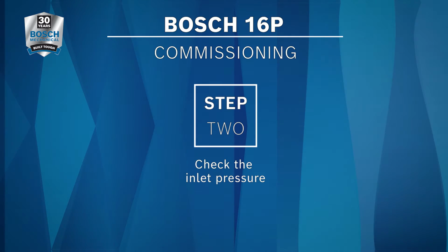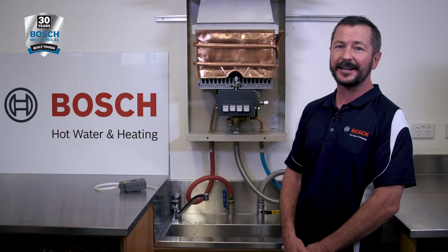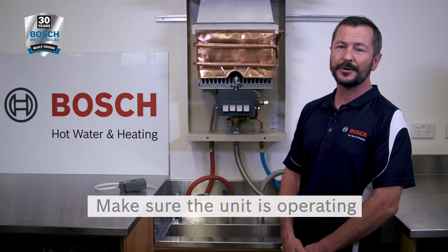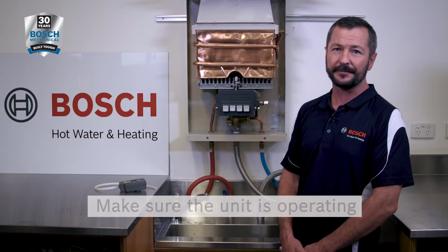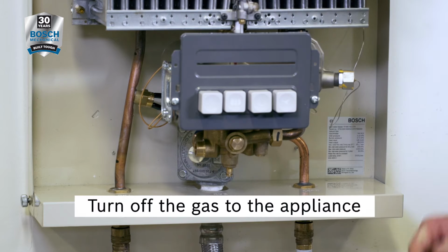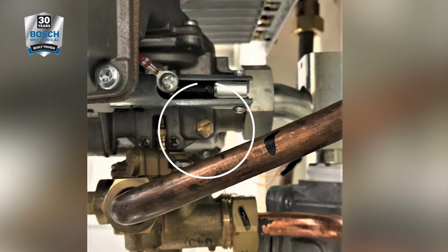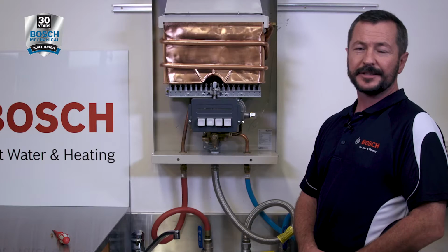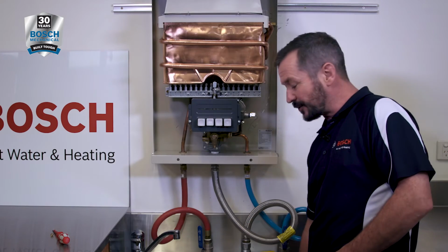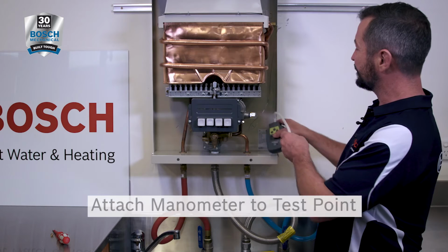Once we have the maximum flow rate set, the next step is to check that we have enough inlet gas operating pressure. It's important to check the pressure while the unit is operating. Turn off the gas to the appliance and loosen the sealing screw of the test point. With the test point sealing screw removed, the next step is to attach your manometer to the test point.